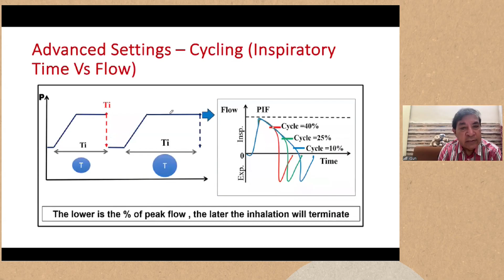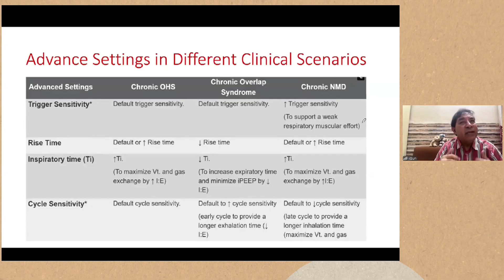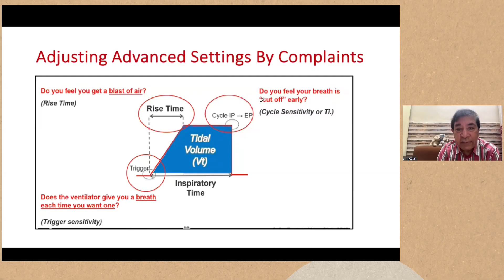So you could see that we can have different settings for trigger sensitivity, rise time, inspiratory time, and cycling for OHS, for overlap syndrome. Different situations of hypoventilation require different settings, and this is basically done to improve synchronization between the patient and the machine. That's how you optimize the synchrony by asking the patient about triggering. Does the ventilator give you a breath each time you want? That means the triggering is occurring properly or not. Then second, rise time. Do you feel you get a blast of air? That means the rise time is short, so you can adjust it. And do you feel your breath is cut off early or late? Accordingly, you can adjust all these things.